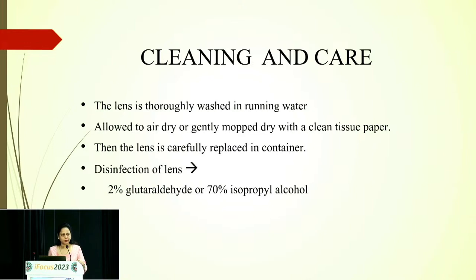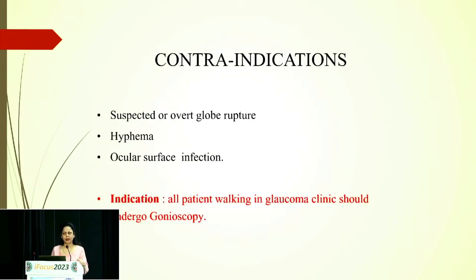The minute you start using any instruments, the first thing that comes is the washing or the cleaning of that instrument. And when it comes to gonioscopes, definitely we all know, immediately go and wash it with soap and water. That will suffice in your OPDs. And for disinfection, later in the day, you can go for a 2% glutaraldehyde or 70% isopropyl alcohol.